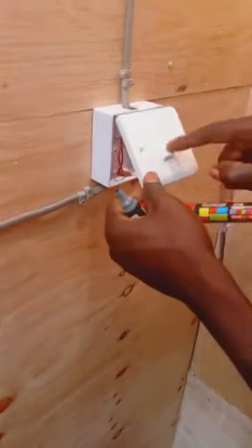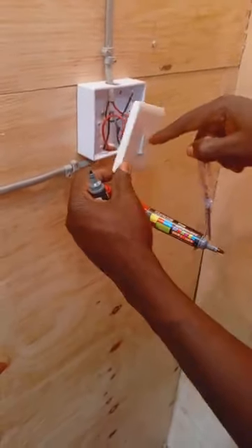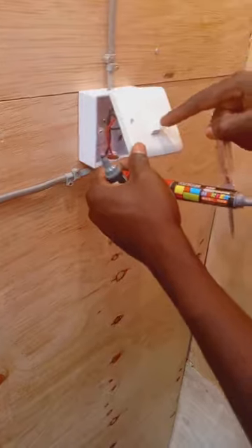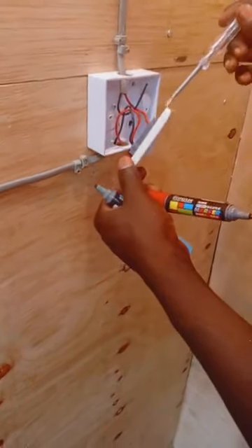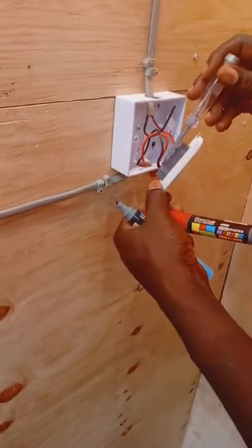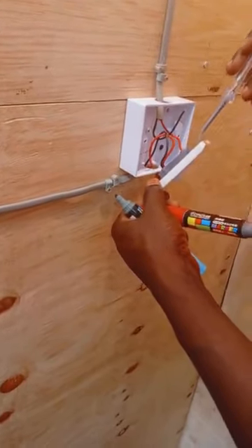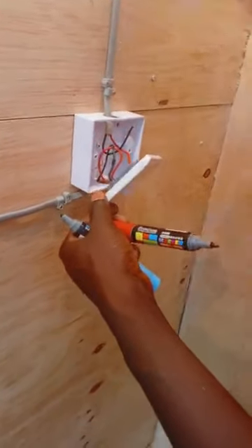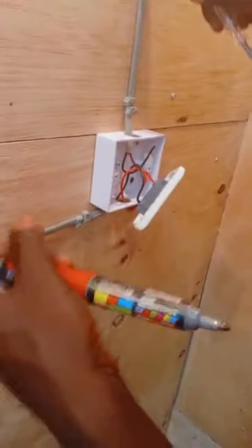Now, why is it that this switch is off and it is giving light? It is because when the switch is off, its common is continuous with the L2, and this L2 is having power. So it means that this lamp feed has power. That is why we are able to register light. Now let's go to the next thing, and that is the next theory about the intermediate switch, which is on.